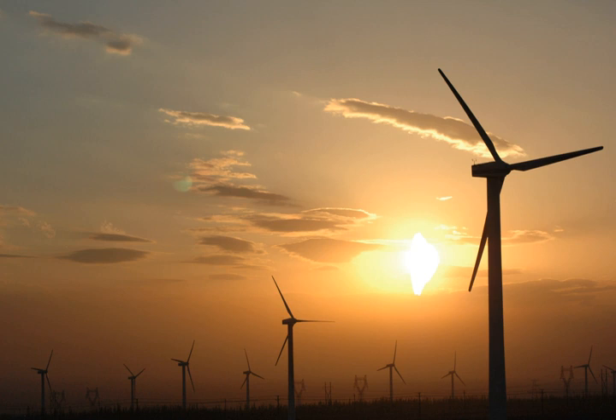GE has installed a prototype wind turbine with onboard battery similar to that of an electric car, equivalent of 1 minute of production. Despite the small capacity, it is enough to guarantee that power output complies with forecast for 15 minutes, as the battery is used to eliminate the difference rather than provide full output. In certain cases, the increased predictability can be used to take wind power penetration from 20 to 30 or 40%. The battery cost can be retrieved by selling burst power on demand and reducing backup needs from gas plants.